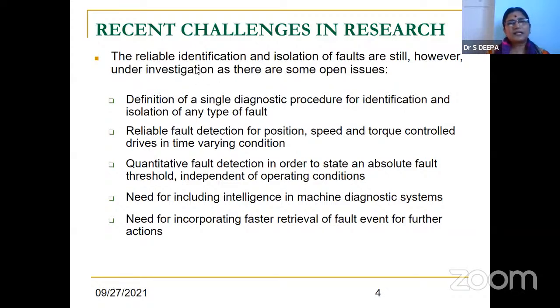Reliable identification and isolation of faults are still under investigation, as there are some open issues. Just as by seeing the pulse you can detect the condition of the human body, there should be a single diagnostic procedure for identification and isolation of any type of fault. Reliable fault detection for position, speed, torque, and controlled drives in time varying conditions. You will have different loads at different times, different speeds.